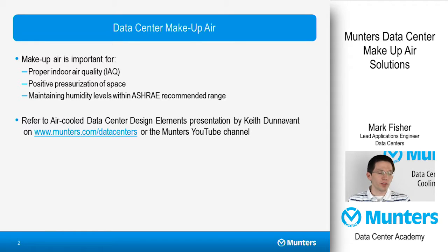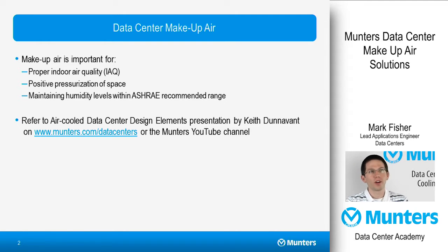Makeup air is important for three reasons. One, to have proper indoor air quality in the data hall. Two, to have proper positive pressurization of the space. And three, to maintain the humidity levels within the ASHRAE recommended range. These points have already been covered in more detail by Keith Dunnavant in a separate session video called 'Air-Cooled Data Center Design Elements,' available on YouTube and also our webpage.